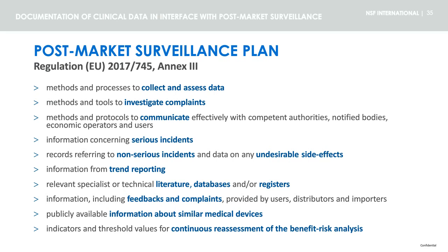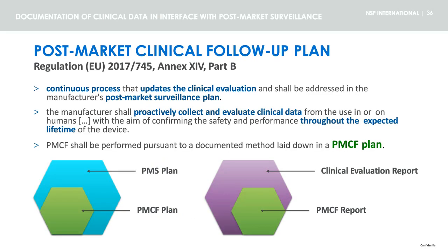Data collected following the post-market surveillance plan are potentially important clinical data to be considered in the clinical evaluation. The post-market surveillance plan should also address post-market clinical follow-up activities. PMCF is a continuous process to proactively collect and evaluate clinical data throughout the expected lifetime of the device, such as the periodic performance of literature search or user surveys.